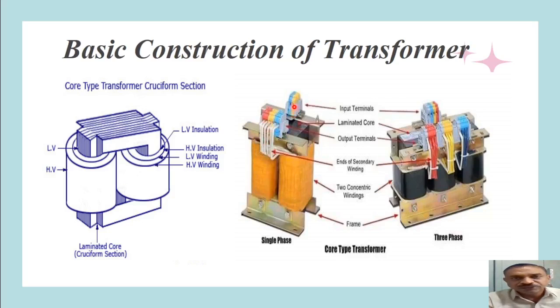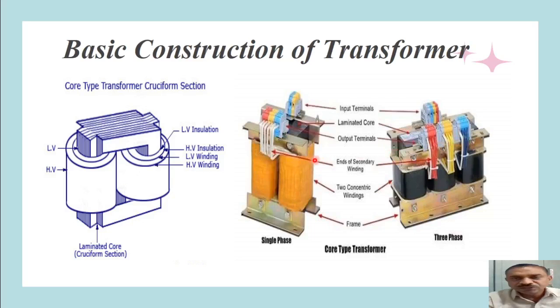The output terminals consist of a number of terminals because, as per requirement, we can provide tapping on the secondary winding to get different voltage outputs. There is a single input but we can get multi-level output voltage. For the three phase core type transformer, for each phase — R, Y, and B — we have three pairs of LV and HV windings. The primary windings connected to the supply system have terminals here, and the secondary winding terminals are on the front side with multiple output terminals for different voltage levels.